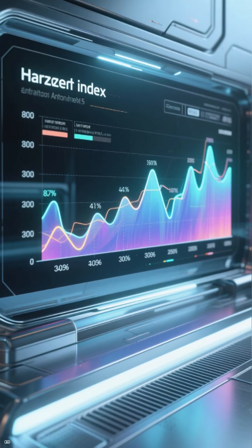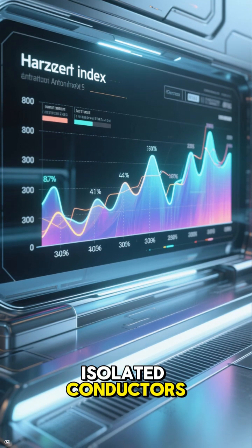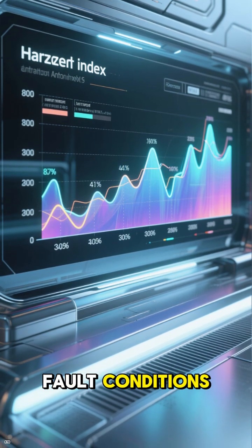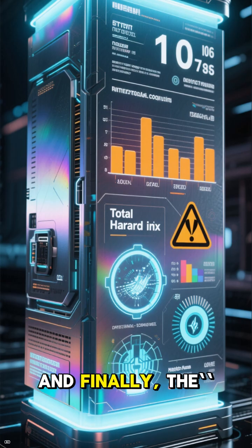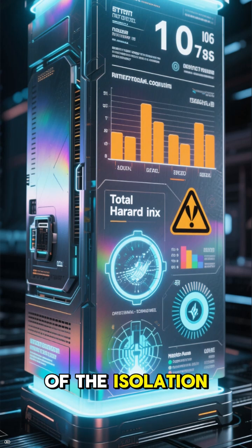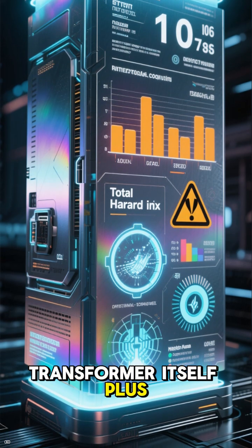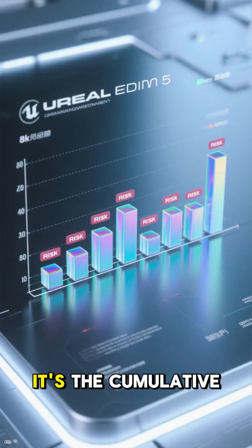Next up is the hazard index. This term refers to the total potential current that could flow from the isolated conductors to ground under fault conditions. It's essentially a measure of the system's leakage current. And finally, the total hazard index is the sum of the hazard index of the isolation transformer itself, plus the hazard currents from all the equipment plugged into that circuit. It's the cumulative risk of the entire setup.